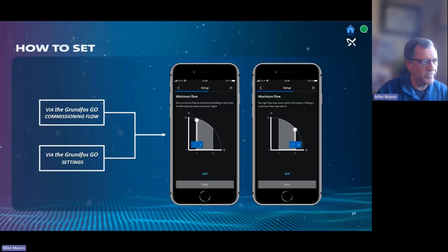You can set minimum flows and maximum flows. I think this is good if you're going to do an auto adapt, and maybe you don't want the pump to ever go below, for example here, 1 gallon a minute. Just tell the pump never go below a gallon a minute. It'll still continue to fluctuate and change its speeds as it's set for that setting, but never go below that gallon a minute. Or you can set a maximum flow as well.